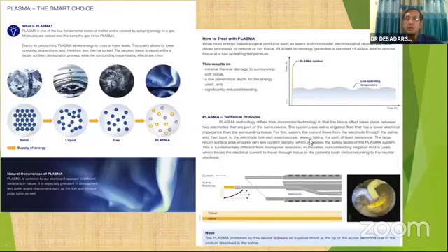I'll be speaking on the bipolar TURP. Most of the time there is a lot of nomenclature like bipolar, plasma, kinetic, or saline TURP. It's all the same. Bipolar means both the electrodes, the active and passive, are in the same place, and the current doesn't pass through the patient's body plate. Yes, the medium is saline. That's the reason it is called a saline TURP.